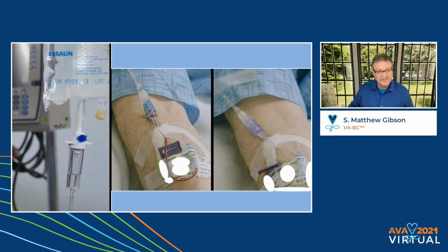Now, what you may say is, well, it's infusing. Well, yes, it is infusing, in fact, but there are times where the pump goes off, and people don't really understand how pumps work. If you've got 50 milliliters an hour, this is not a continuous stream that's spraying into the catheter. It's graduated. It'll infuse a few drops or a few microliters or a milliliter, and then stops. It's incremental. So every time that pump stops, then the pressure inside may start to overpower the pump pressure and start to reflux blood up into the catheter.